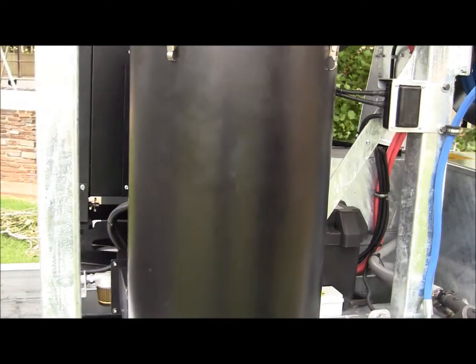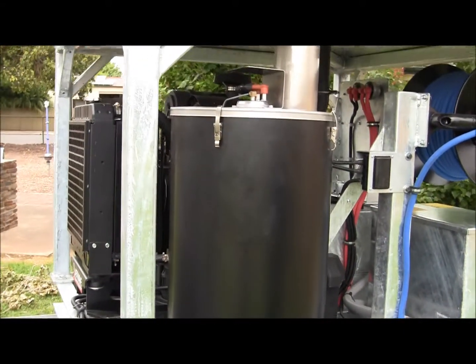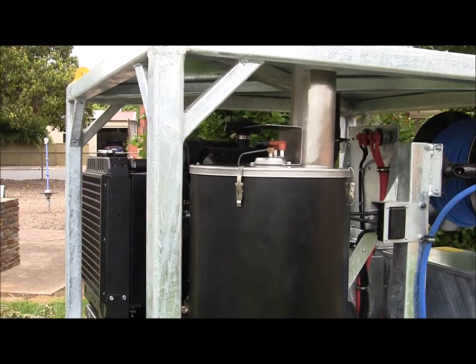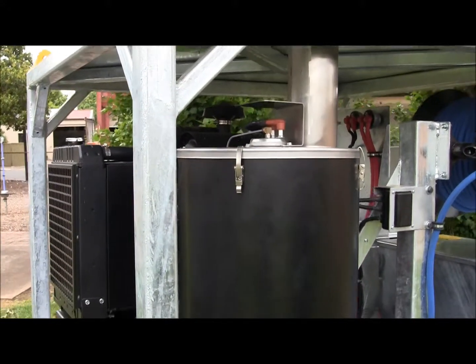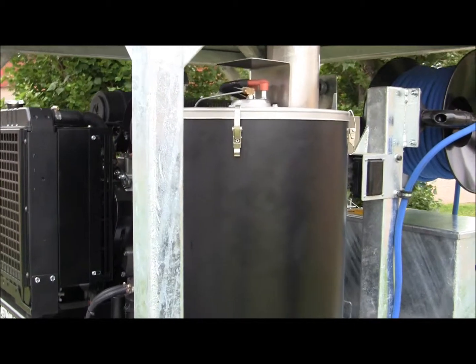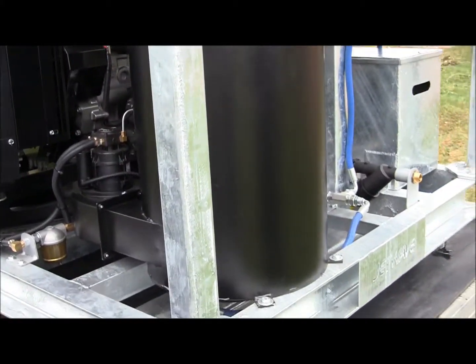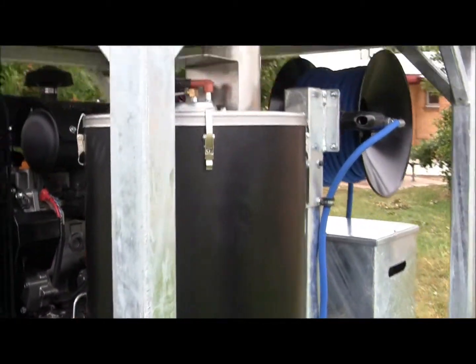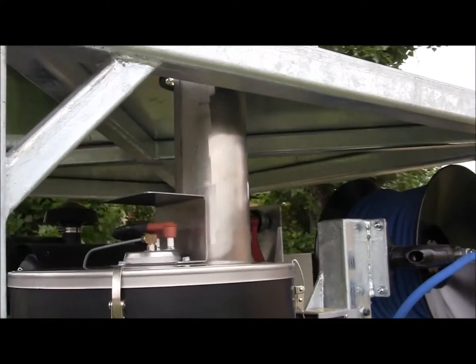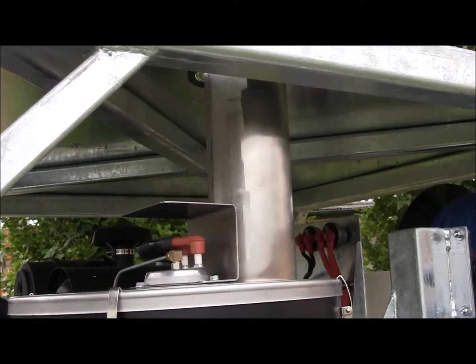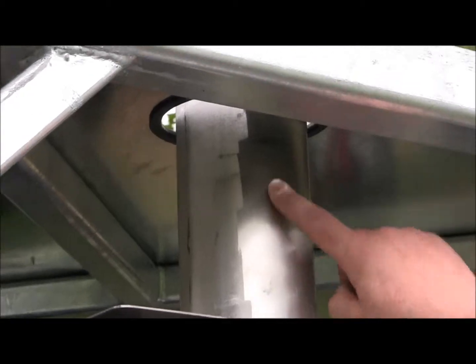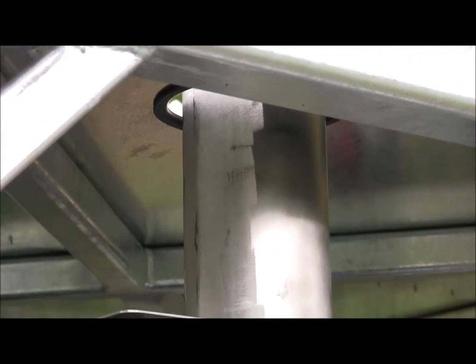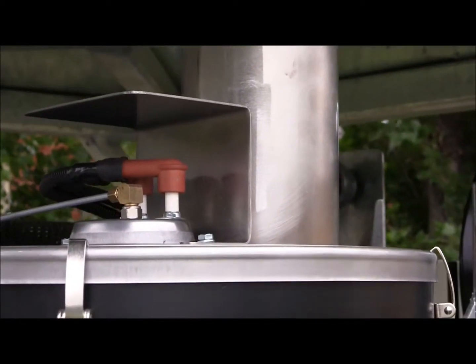This particular unit's got what we call the large vertical V4 burner. This particular unit is actually rated to 30 litres per minute with the seamless steel roll coil heating coil inside. This unit is with the top cover on. We have to ventilate the unit up and out and exhaust the engine and the burner up and out of the top of the frame cover. And you can see here the stainless steel extended exhaust flue running out of the top of the frame.